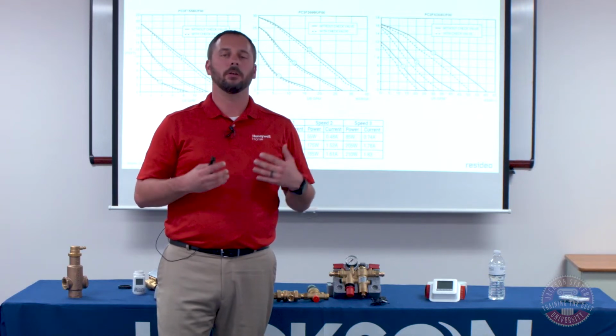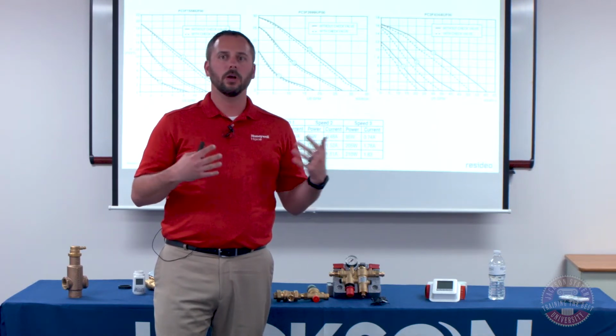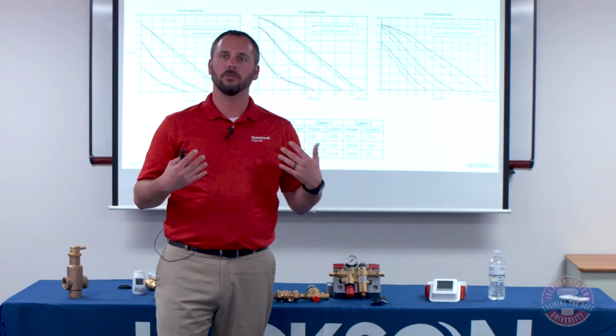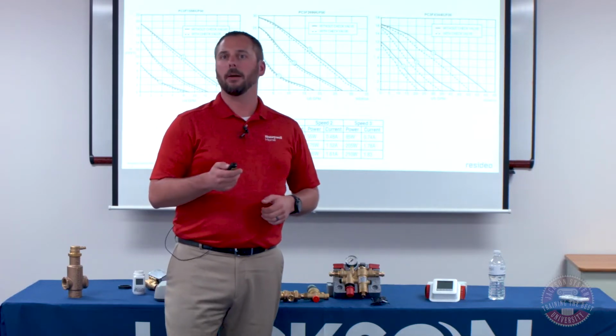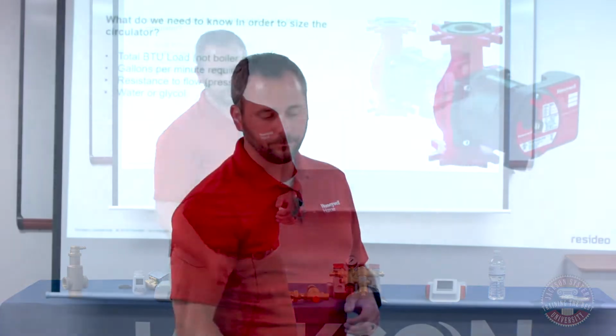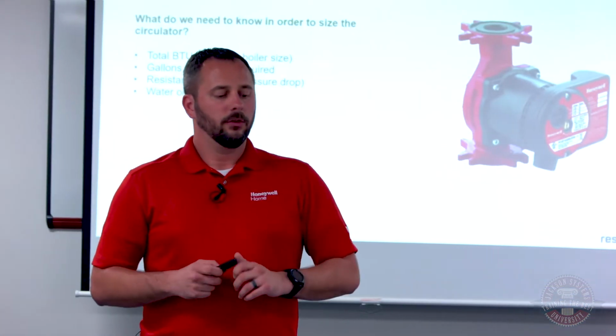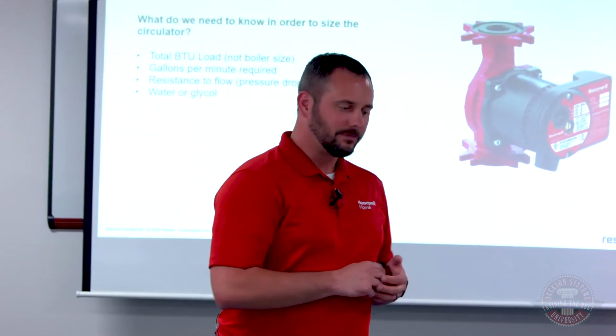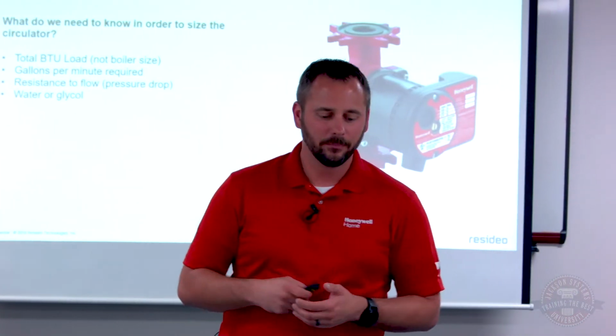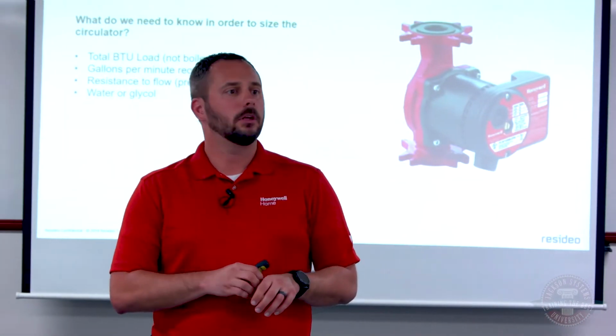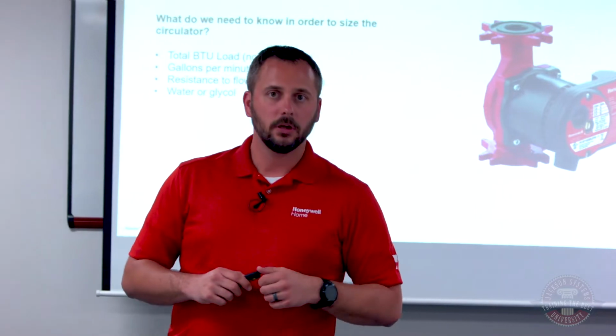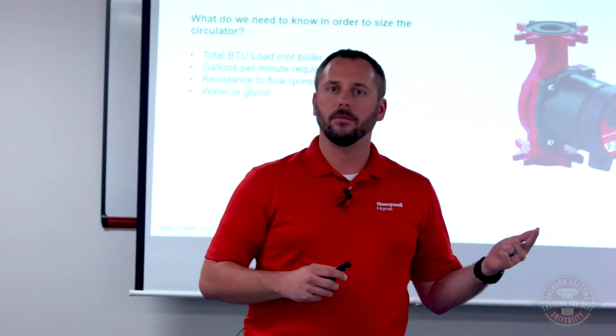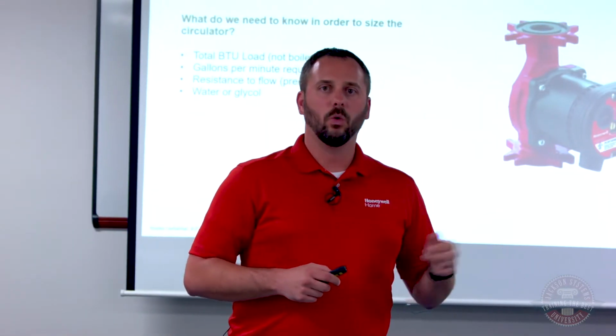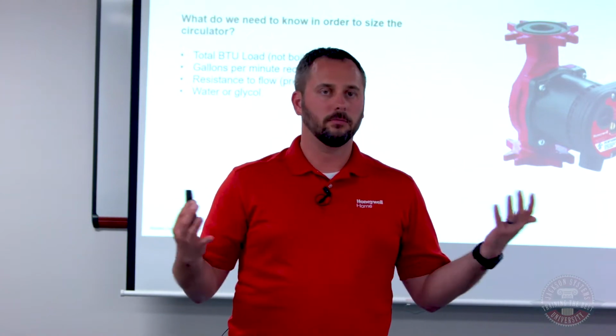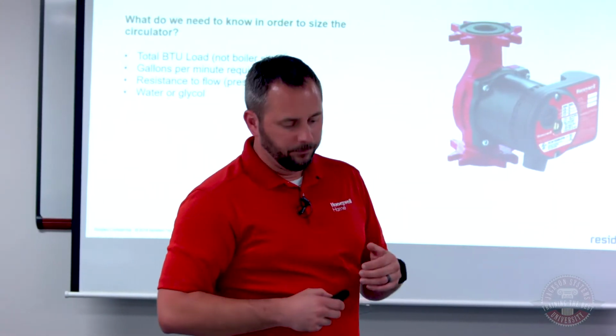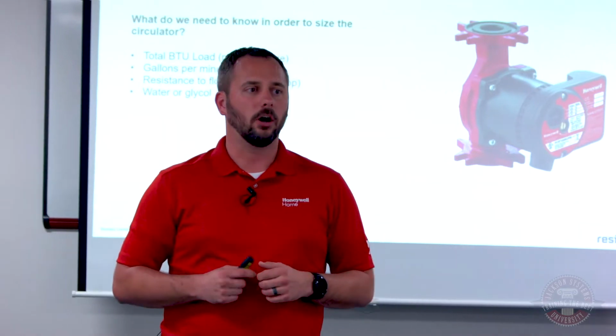But they're very common circulators that those 2 numbers are actually European measurements that pertain to flow rate and head pressure, but very commonly spoken in the heating world. So sizing pumps, or circulators as we call them. A couple of things you need to know. You need to know what the BTU load is. In turn, what the gallon per minute flow rate is going to be, what your resistance to flow will be. So in our world, we use feet of head. And then if you're using water or glycol.